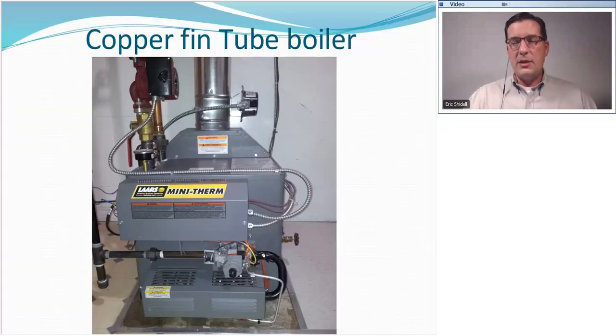The next boiler we're going to discuss is called the copper fin tube boiler. Copper fin tube boilers are much smaller than cast iron boilers. This boiler right here is really about the size of a big lunchbox if you're a big person. You could probably pick this up with one hand and walk around with it. I'm exaggerating, of course. This is probably about 2 feet wide by 2.5 feet deep by maybe 2.5 feet tall. It's really not physically large.